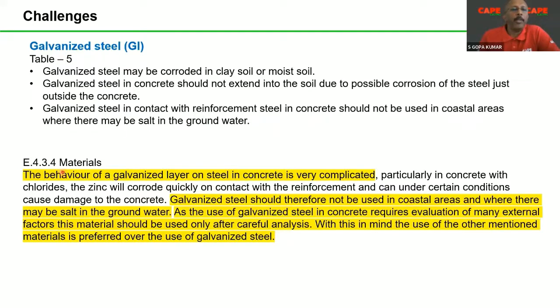In the clause E 4.3.4 on materials, the behavior of galvanized layer on steel in concrete is very complicated. I will just read the highlighted explanation. Galvanized steel should therefore not be used in coastal areas and where there may be salt in groundwater. That is one point. The second is, as the use of galvanized steel in concrete requires evaluation of many external factors, this material should be used only after careful analysis. So using GI for this purpose inside concrete has to be carried out after careful analysis.